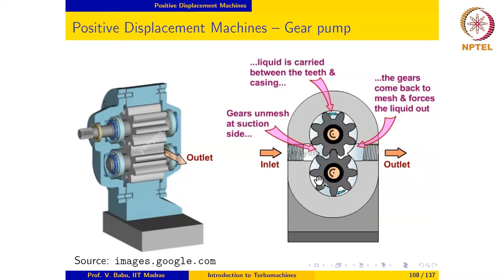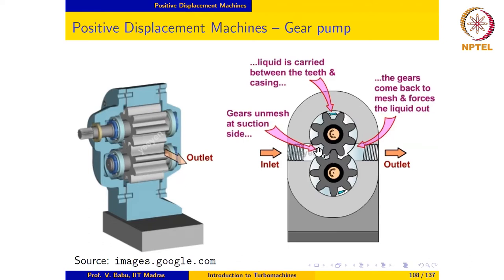When a pair of teeth come up to the inlet point, the gears are completely unmeshed and so the volume available between the gears is at a maximum. A certain chunk of fluid is then taken into this volume. As the top gear moves up and the bottom gear moves down, half of the chunk of fluid is carried along in the passage on the top and the remaining half is carried along in the passage below. This is why we call it a displacement pump — the fluid is physically carried by the gears from the inlet to the outlet side.